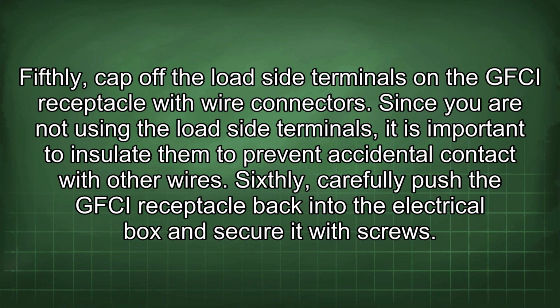Fifthly, cap off the load side terminals on the GFCI receptacle with wire connectors. Since you are not using the load side terminals, it is important to insulate them to prevent accidental contact with other wires. Sixthly, carefully push the GFCI receptacle back into the electrical box and secure it with screws.